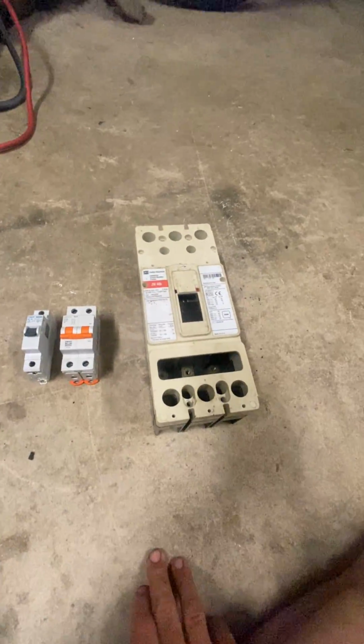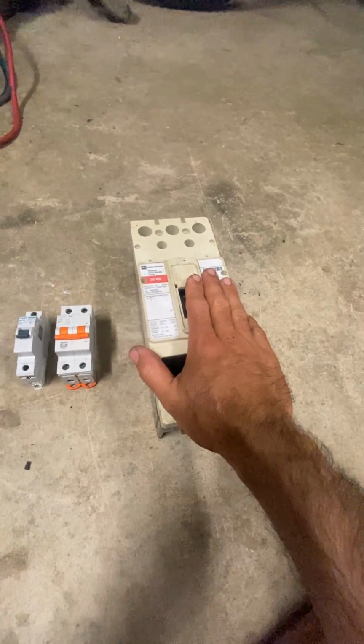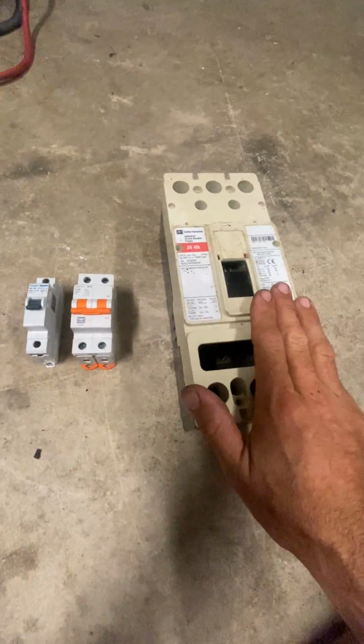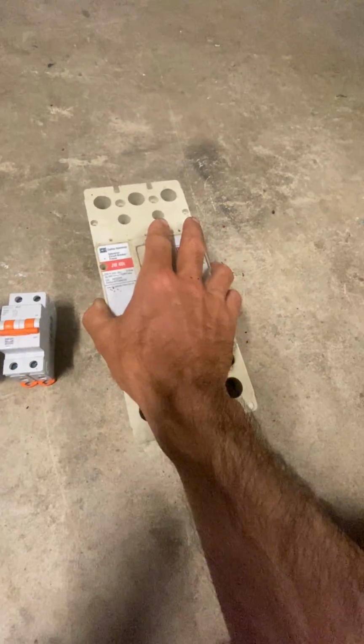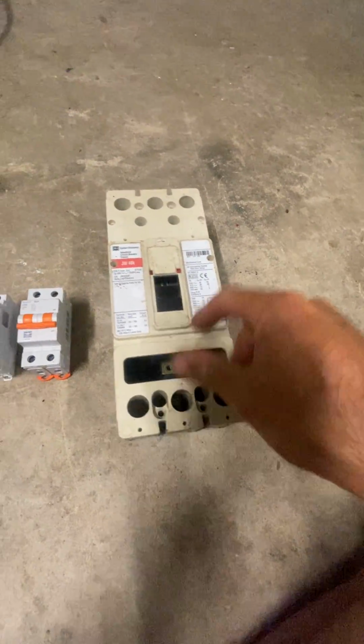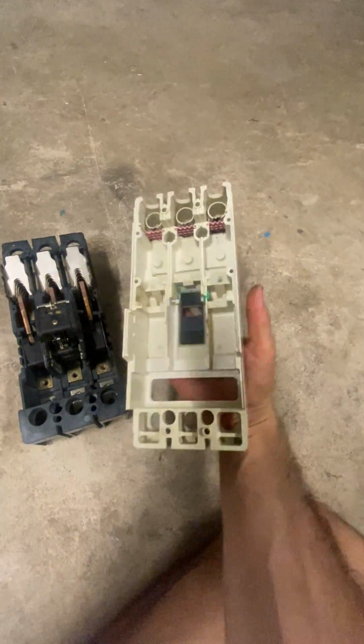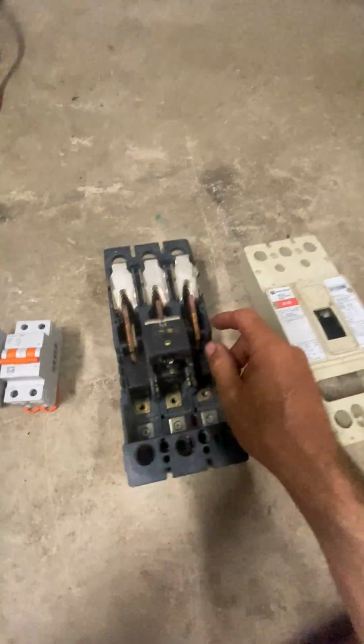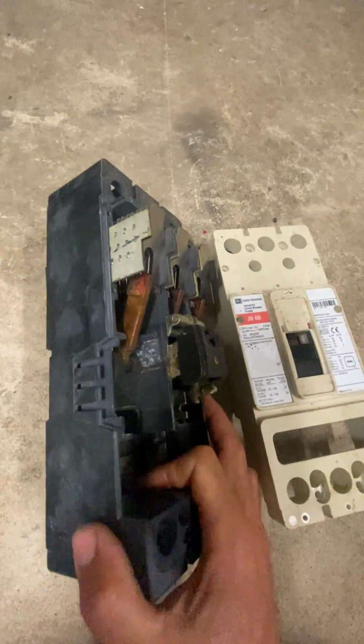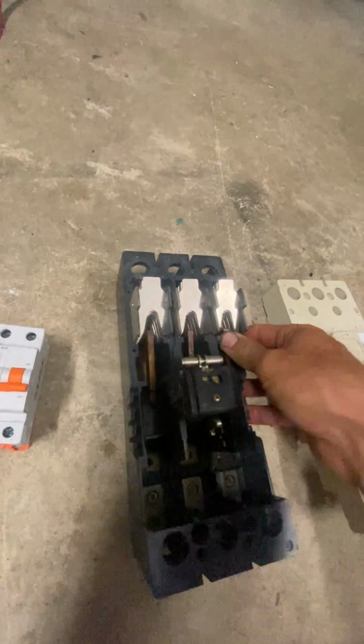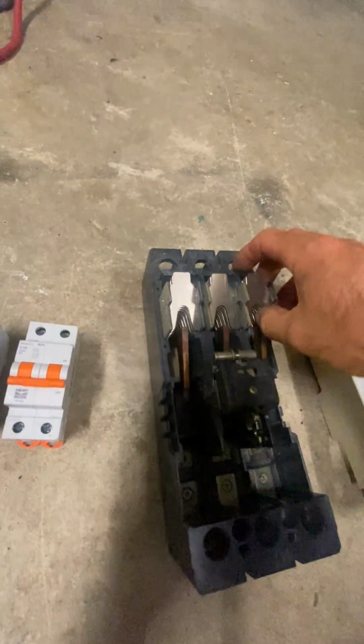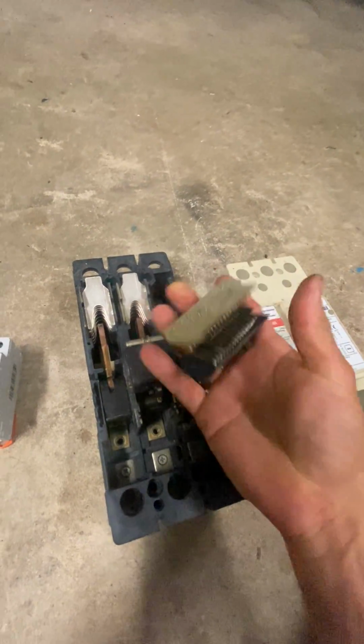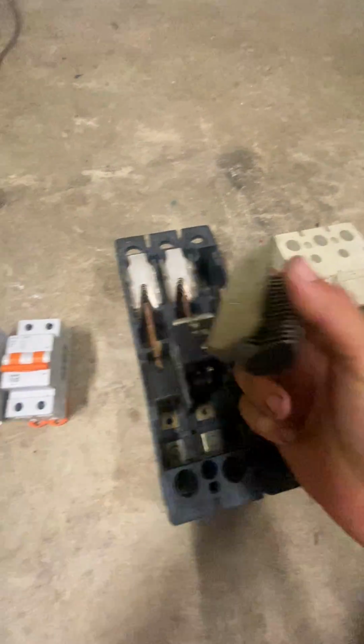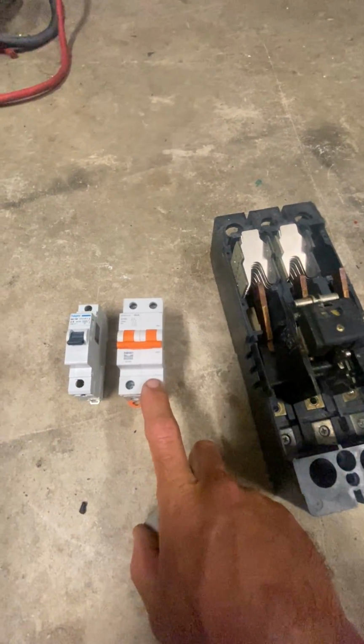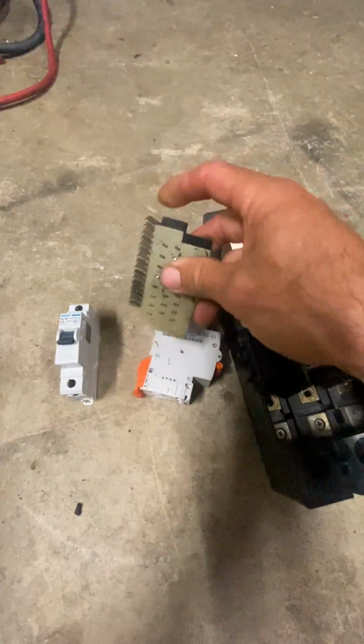So with regards to these, this breaker here gives a good example of what's inside these two guys, but this is pretty much on steroids. Because you have to put something inside here for the shunt, you can pull these apart, and then inside them you can see the whole mechanism in there. So these here are basically the switch mechanism, and these here are your arc chutes. This is a larger version of what you have in here. There'll be a very, very small version of this inside these guys here.